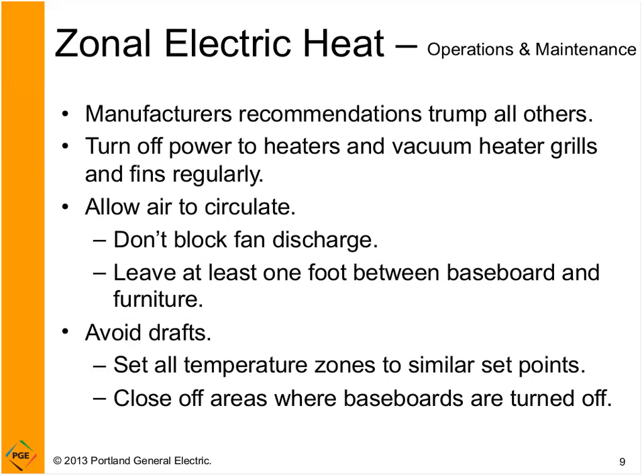Operations and maintenance for zonal electric heat. Always refer to the manufacturer's recommendations. The manufacturer is going to trump all others. But in general, turn off power to the heaters to vacuum the grills and fins regularly. Allow air to circulate, and don't block fan discharge.